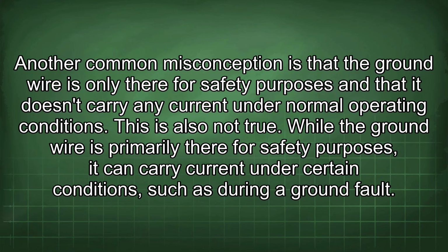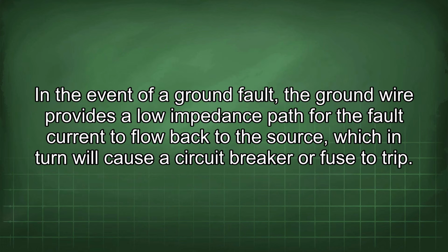Another common misconception is that the ground wire is only there for safety purposes and that it doesn't carry any current under normal operating conditions. This is also not true. While the ground wire is primarily there for safety purposes, it can carry current under certain conditions, such as during a ground fault. In the event of a ground fault, the ground wire provides a low impedance path for the fault current to flow back to the source, which in turn will cause a circuit breaker or fuse to trip.